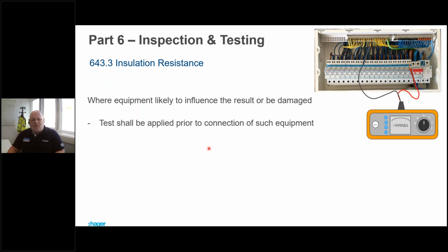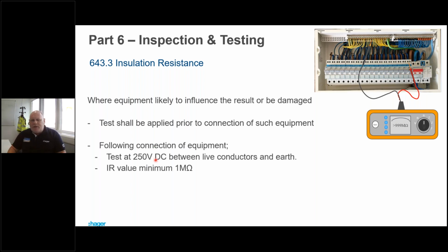Because we've got transformers connected, we've got electronic devices, we might get some very strange readings there, and sometimes putting 500 volts through these devices could damage them as well. So we do the test at 500 volts before they're connected. Following their connection, we're going to test at 250 volts, and we're going to look for a minimum IR value of 1 megohm.